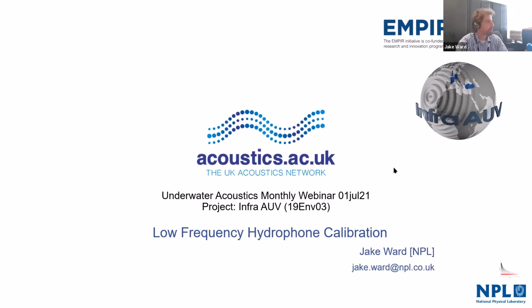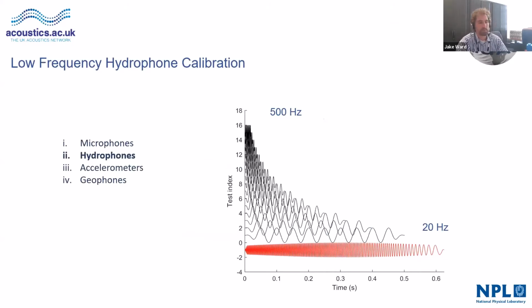So this is different from the frequencies we're used to. I guess our understanding as human beings of frequency comes from our hearing system, and we don't really know much about below 20 hertz from an experiential stance. So it's an interesting problem to calibrate hydrophones at these frequencies, because fundamentally the wavelengths are extremely long, and so we can't use the techniques of using tanks to transmit and receive sound. We have to come up with different approaches to calibrating hydrophones at low frequency.